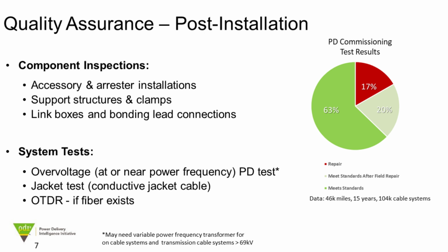By far, the vast majority of faults are associated with voltage transients. While overloading can be an issue, overheating connectors can be an issue, the vast majority of issues from an operation standpoint are associated with transients, voltage transients. So making sure our arresters are in place, the surge arresters, because it's not just lightning, it's the everyday surges that are going to stress the system, and we need to protect against extreme voltage. So making sure they're installed properly with proper lead lengths and in proper positioning, right sizing, and so forth.